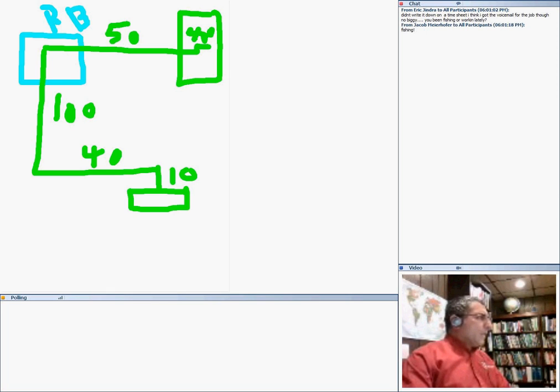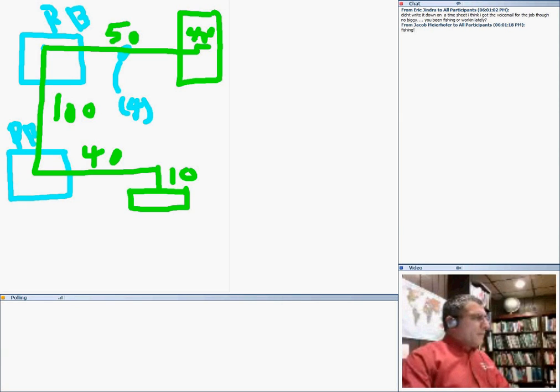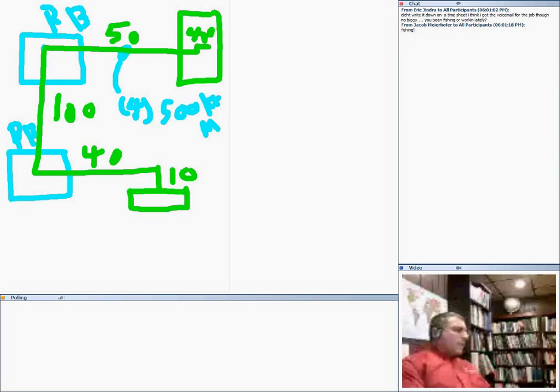And based on the situation, you pull your conductors to this point. From this point you pull them through the conduits. You might need another pull box right here. It wouldn't hurt to put pull boxes in these corners. And remember, if it's 400 amp, you're talking about 4 conductors that you're pulling in this feeder, 500 kcmil each. So 4 conductors, 500 kcmil each, 50 feet, and then 100 feet, then 40 feet, then 10. It might be a very good idea to put these pull boxes to make it easier for you to pull these conductors. What do you guys think about the pull box? So these are not baby conductors.